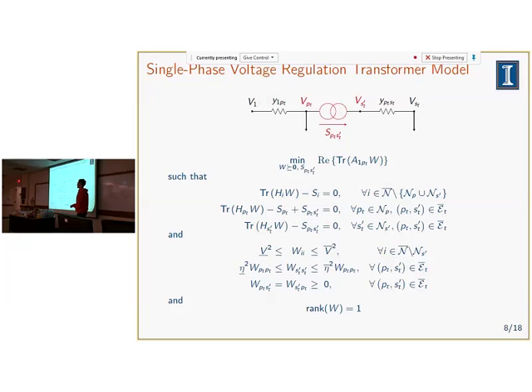No, but what they are physically, I'm not sure if they got that they are the limits of the taps. Yeah, it's the ratio for the taps, how they correspond. So for example, if there's 16 taps up, depending on what it is, I usually use it as 5/8%, so one tap is 5/8%, and it ends up being plus minus 10% with the 16 positions.